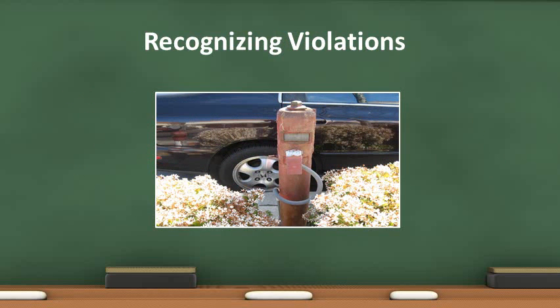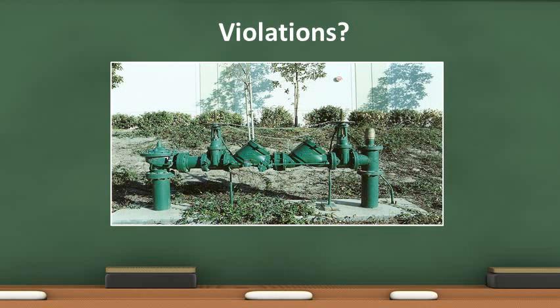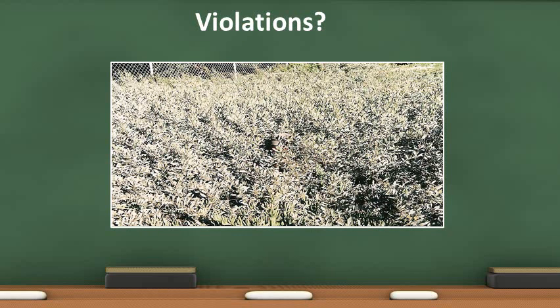The following slides show sprinkler system violations. How many can you spot? The shutoff wrench is missing and the sight glass is unreadable. There is no sign indicating building served. Remember that breakaway locks are not required when a tamper switch is present. The sign indicating the areas served by the control valve is missing. All sprinkler equipment, including this FDC, require at least 3 feet in all directions of unobstructed space and a sign indicating building served.